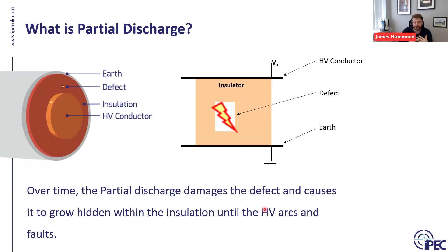So the PD itself tends to happen in phase with the power cycle. On the rising and falling edge, you have these partial discharge pulses. If you've ever seen graphs like these, they're known as PRPD, or phase resolved partial discharge patterns. These are discharges happening on the rising and falling edge of the AC sinusoid. Basically, this is where a certain voltage threshold is exceeded, and then these discharges occur locally. As you can see, it's in line with that phase, so 50 or 60 times per second.